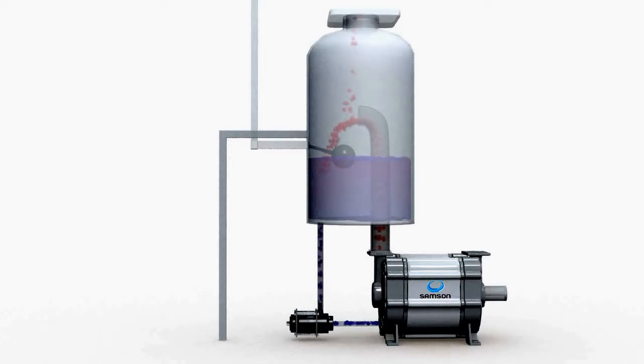In some cases, the reuse cycle will cause heat to accumulate in the service liquid. The accumulating heat will affect the performance of the pump and can ultimately lead to cavitation. To ensure cooling, a temperature-regulating valve can be mounted to monitor the process. The valve can be set manually at the highest temperature chosen for the individual process. If the temperature rises, the valve will open and allow external cooling water to enter the liquid separator, and the excess heat will flow out of an overflow pipe.